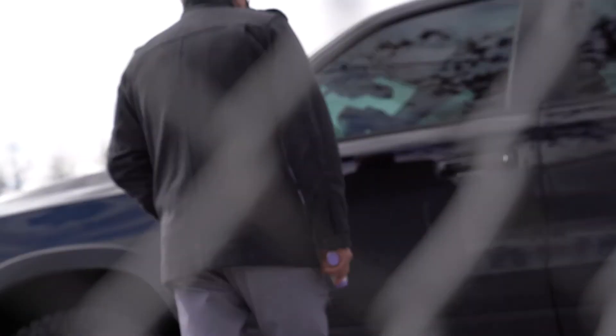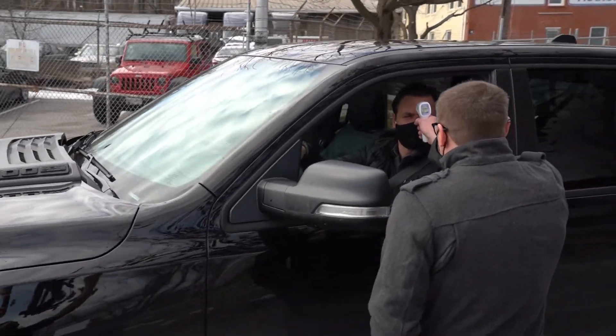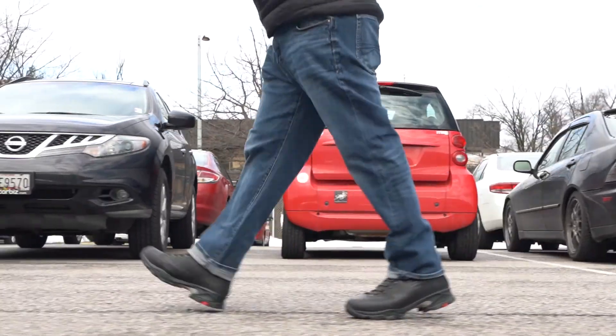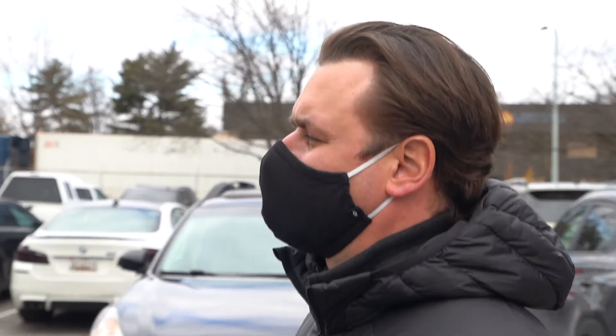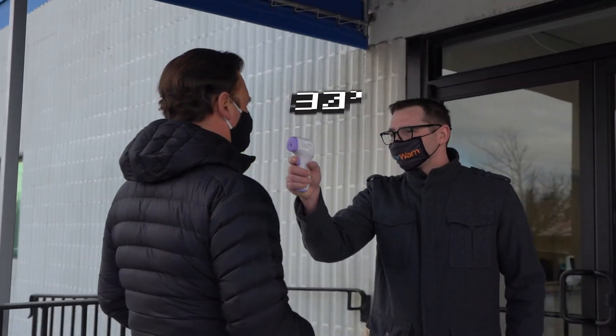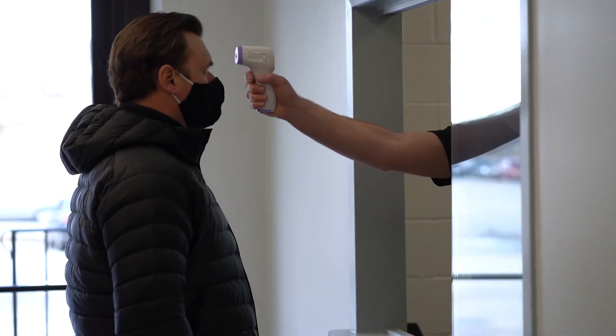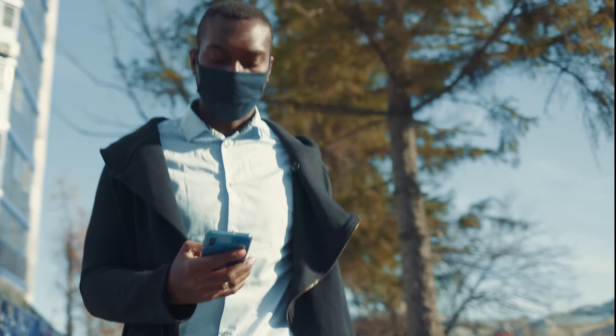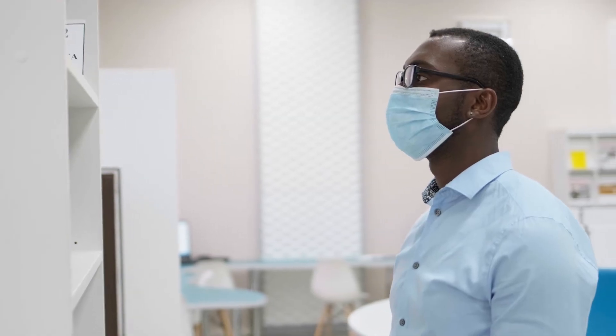Here is a typical staff arrival, arriving in a heated vehicle. Let's see what the scanner reading of the temperature of his forehead actually says before getting out of the vehicle. After parking their vehicle, they typically walk across the parking lot. Many employees arrive early in the morning before the afternoon sun, and they brave the winter chill and more. Now that he has walked across the parking lot, let's see what happens to their forehead temperature as they enter the facility after the forehead has been exposed to the cold air. Now let's see what happens when we retake the temperature of the forehead inside the building. From these results, you can see how the forehead temperature changed drastically from inside the vehicle to the entrance of the building because of the cold. And if it was excessive heat in the summer, the inverse would happen with higher temperatures on the forehead, and again, inaccuracy. So in these climate extremes, infrared skin temperature alone is simply not an accurate way to screen people properly.